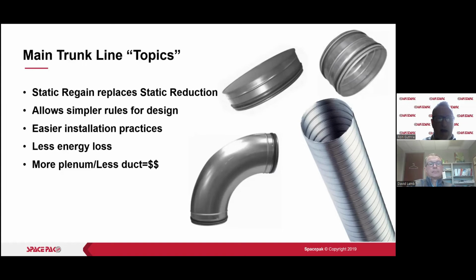All right, static regain, replace the static reduction. We talked about that. Simpler rules for design. We're not reducing as we go. We're running 9-inch round or 8x8 square all the way down, putting a cap on the end. All right, so easier installation. These are very easy to install. You just have to know the things that we're covering today.